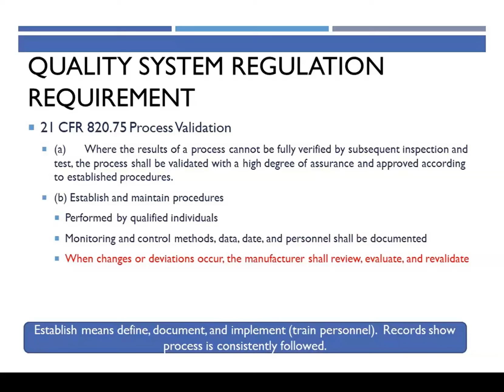Expect the FDA to ask for this information. Don't be surprised. Your procedures need to provide detail on the monitoring and control methods you use, the data, the date, and the personnel who do validation activities. So your procedures should require those things. And they explicitly say when changes or deviations occur, the manufacturer shall review, evaluate, and revalidate. So here we see that validation is not a static thing. It's not a one-time and you're done activity. If there's changes, if there's trends, if there's deviations, you have to review, evaluate, and revalidate.